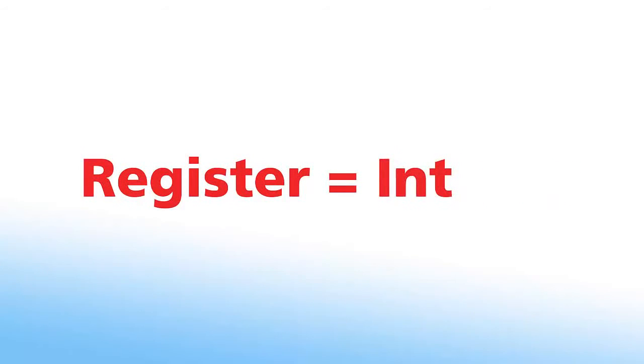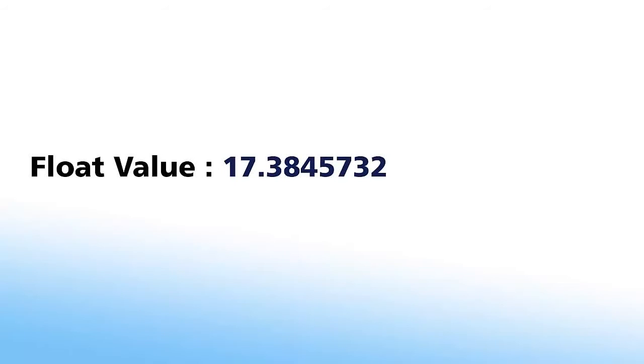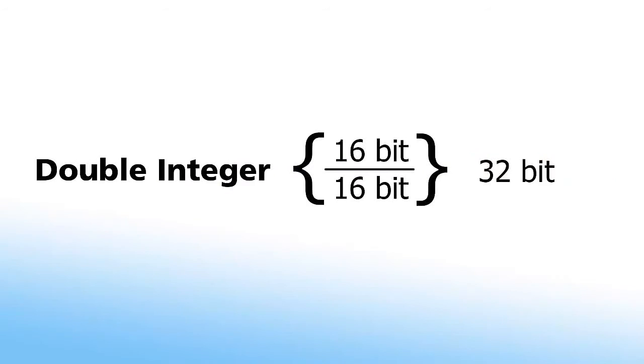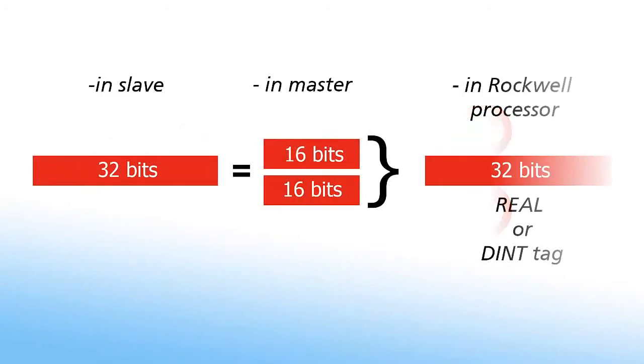There are no registers for floats or double integers, although they can be sent by dividing them into two registers. Float values are any real number with a decimal point that is represented by a 32-bit register. Double integers, or dints, are simply two 16-bit values stacked together, also represented by 32 bits. This presents a small problem since Modbus does not have a float or dint data type. The solution, obviously enough, is that the 32-bit value is broken into two separate 16-bit registers and then recombined into a 32-bit real value. This is accomplished by copying the two 16-bit registers to one real tag in the Rockwell processor.